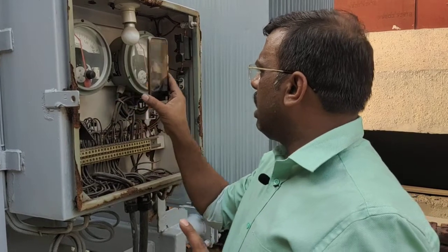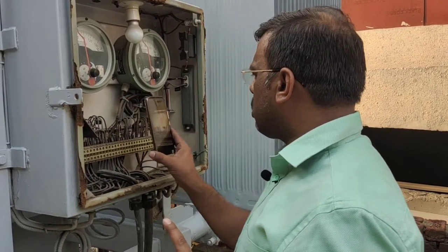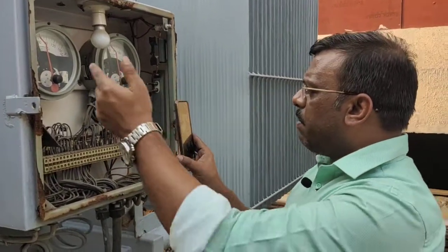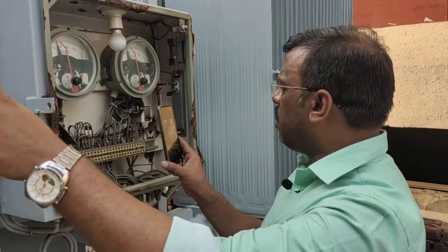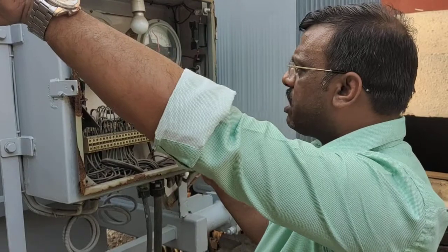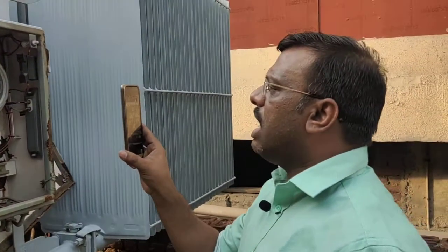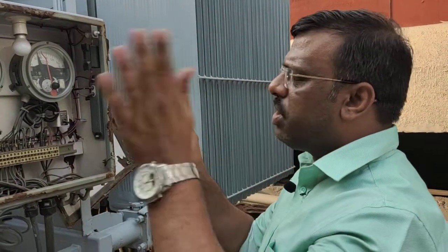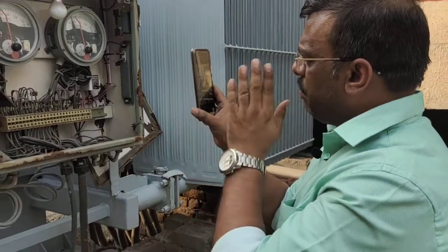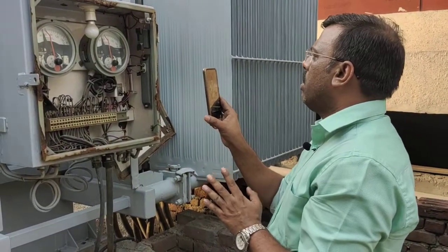This is OTI, yes, this is your WTI, and these all are the control commands which are sensing to the VCB or SF6, and the Buchholz relay command is also directly going to the VCB. So that is a reverse current which is going through a VCB. If there should be any fault arises in this transformer, the direct command is directly going to the VCB to cut off the input supply. Fine.